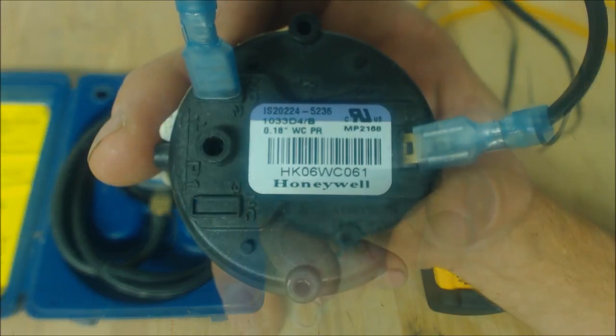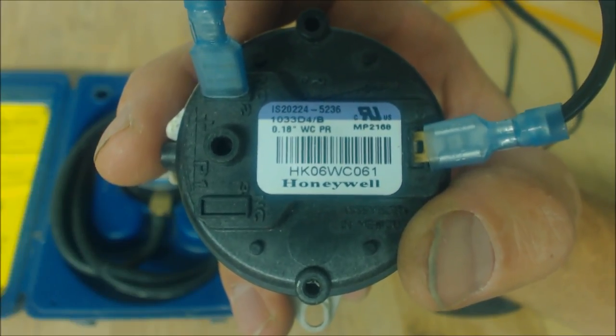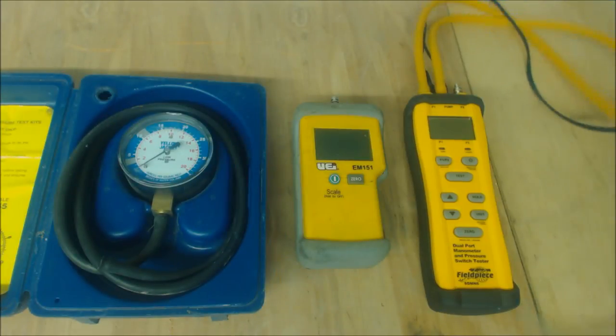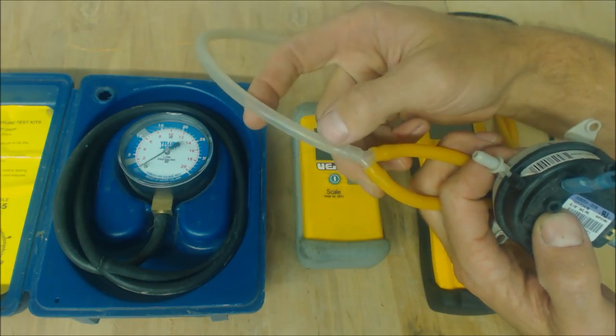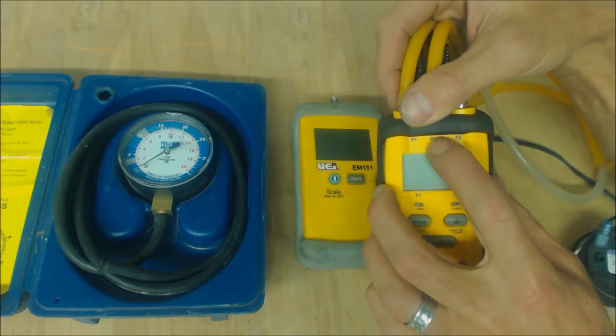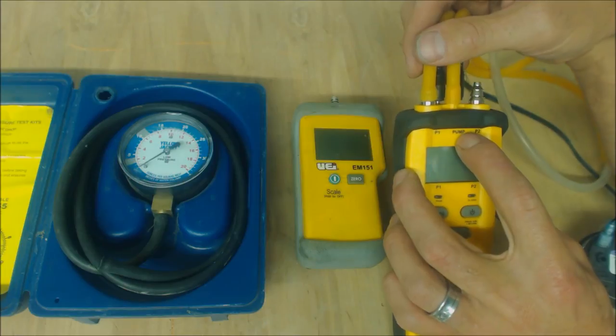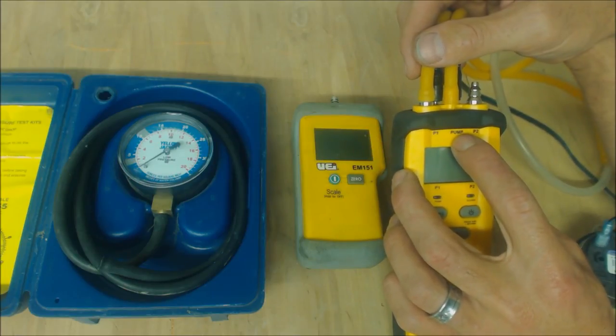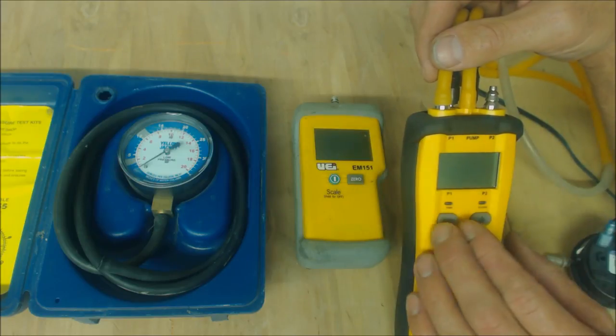This pressure switch is rated at 0.18 water column, so that's what we're looking for. Over here we have a junction from two tubes to one tube. This says 'pump' and this says 'P1.' We're going to use the pump to pump negative pressure and read it at P1.